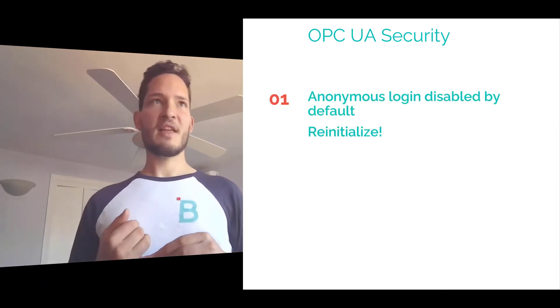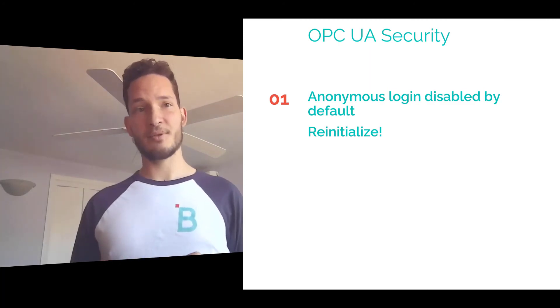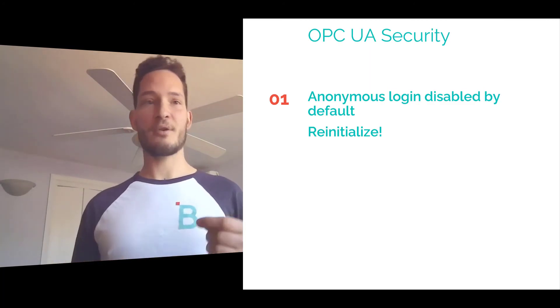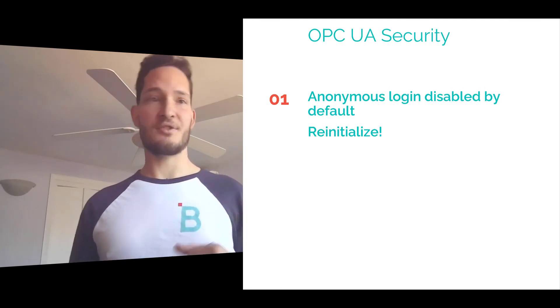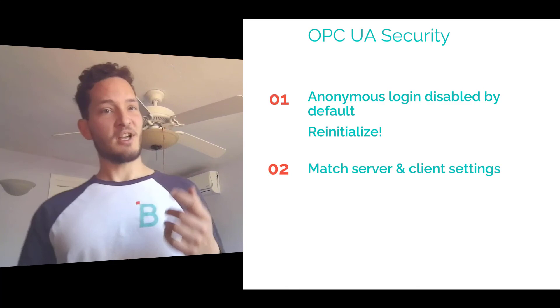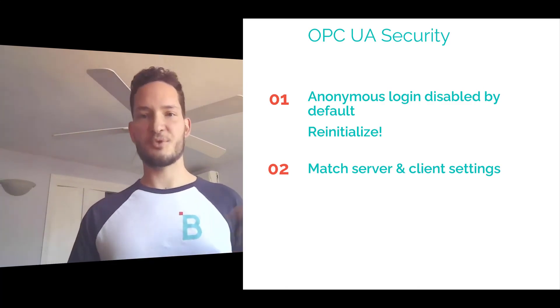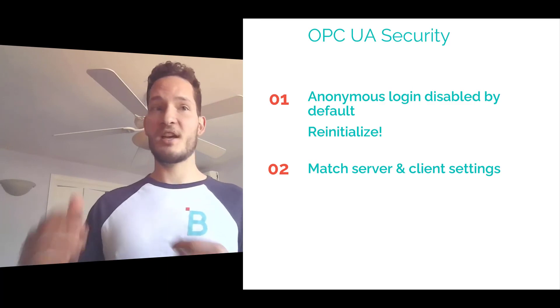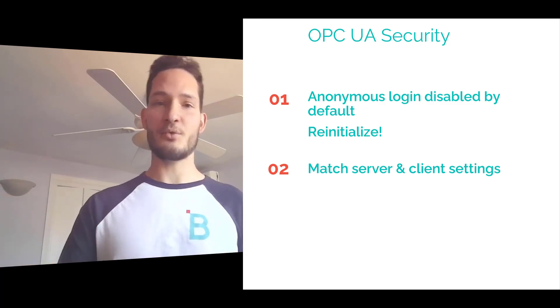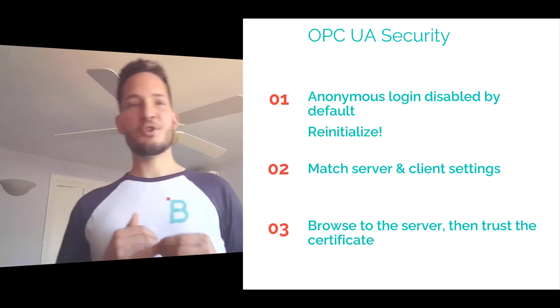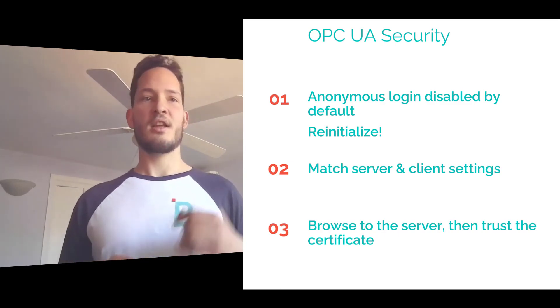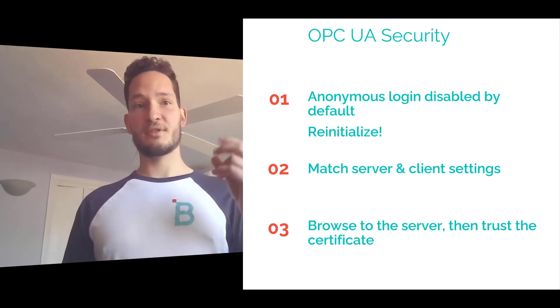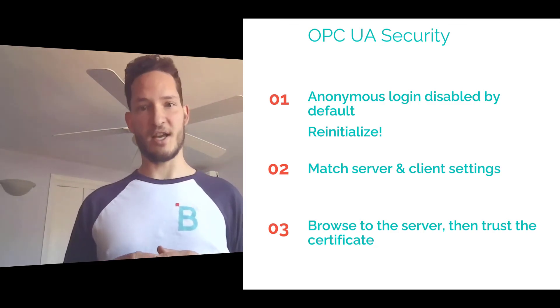Number one, remember that Kepware comes out of the box with anonymous logins disabled. So if you want to log in without a username and password, go ahead and enable this property and then reinitialize your Kepware server. Number two, this seems obvious, but be sure to match your settings between your server and your client's side. So if you have sign and encrypt on your Kepware side, be sure that's reflected on the HiByte side as well. And then the last one is be sure to trust your client's certificate. So if you're still not able to get a connection, double check to make sure that you've accepted the client's certificate on the Kepware server side.